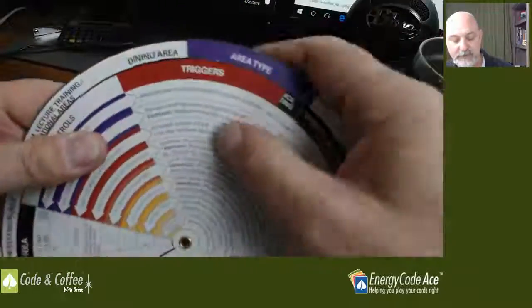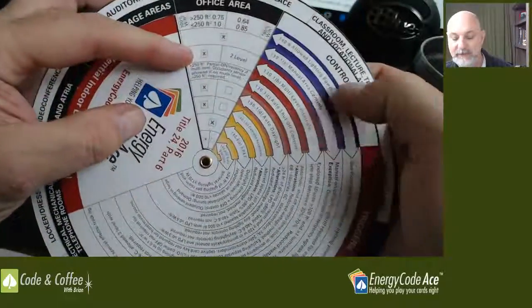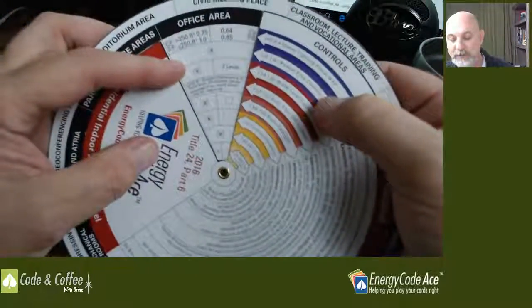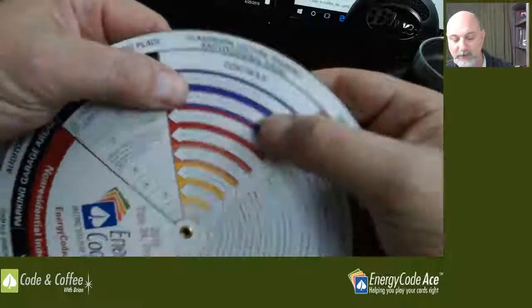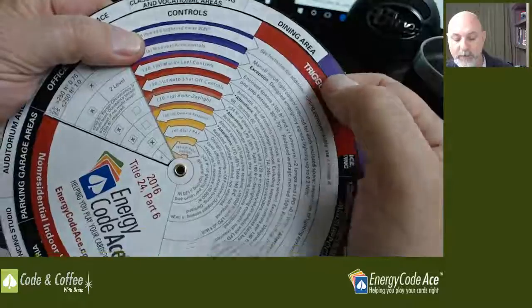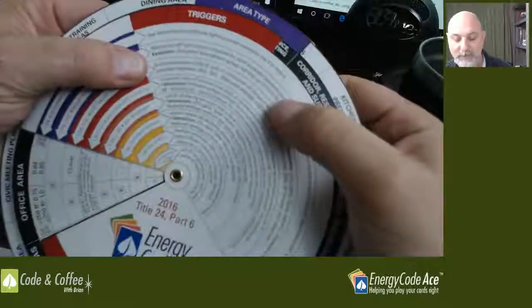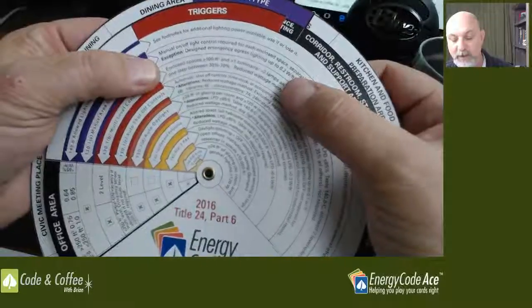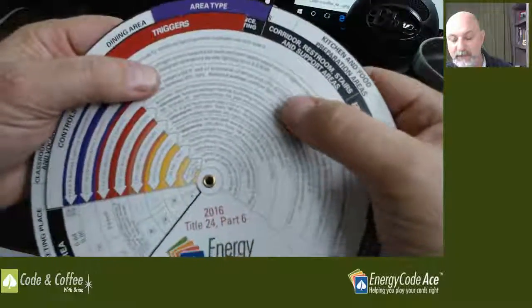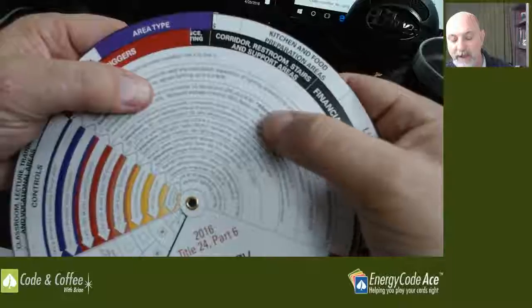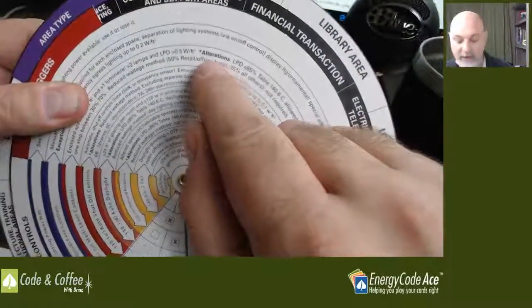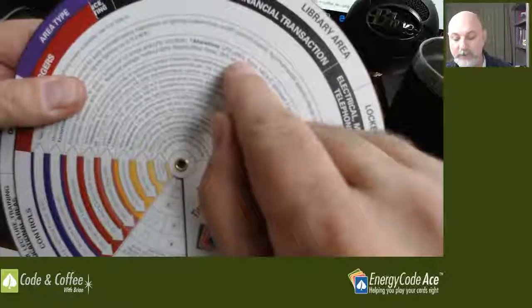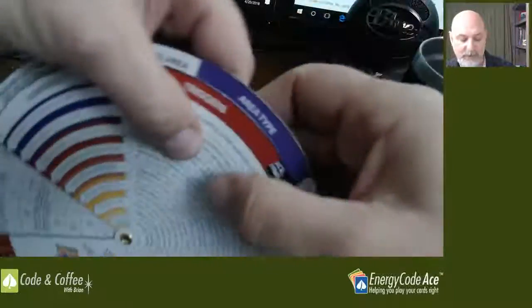Our next layer of lighting controls is multi-level lighting controls. You can see that box is checked here. So we look at multi-level lighting controls, section 130.1b. This applies to enclosed spaces greater than 100 square foot, greater than one luminaire with greater than two lamps, and then lighting power density greater than 0.5 watts per square foot. You can see here, in addition, you're going to have some alteration exceptions. So we'll get to that shortly.